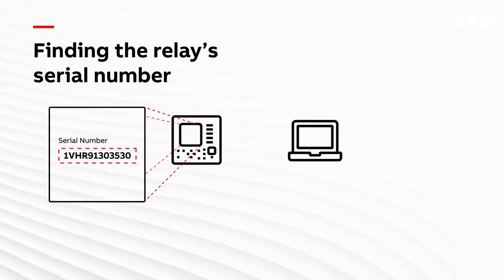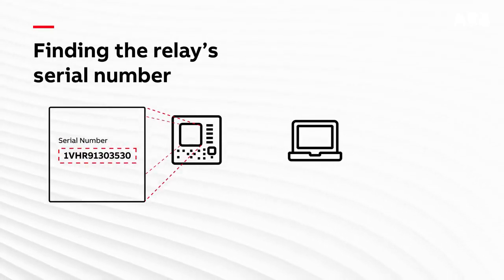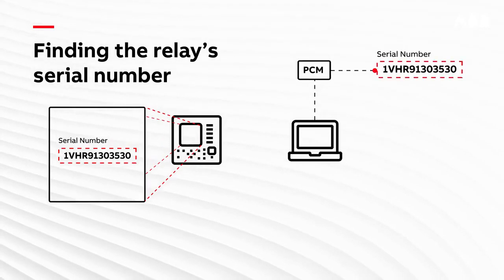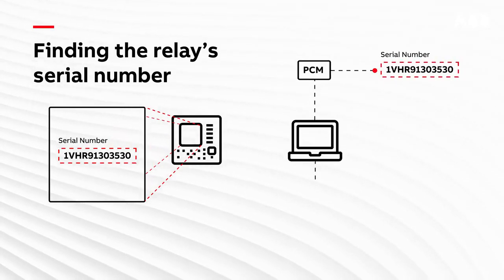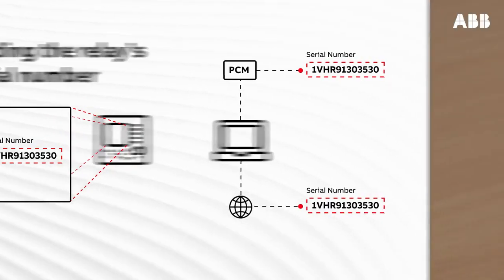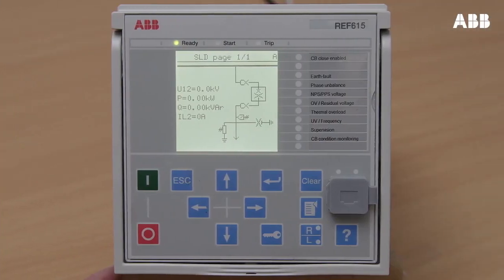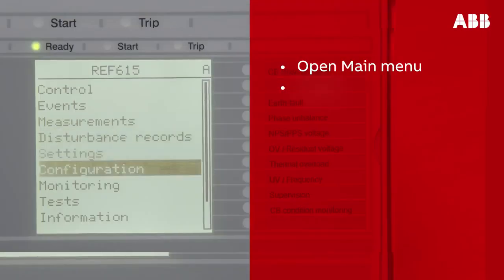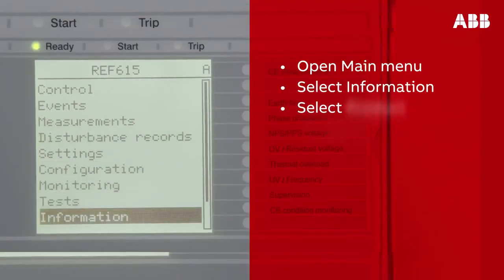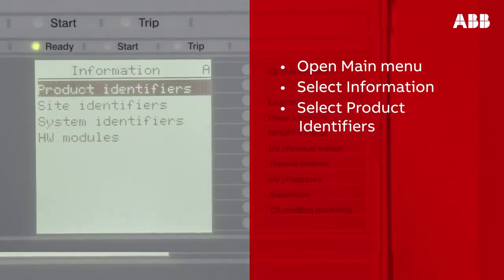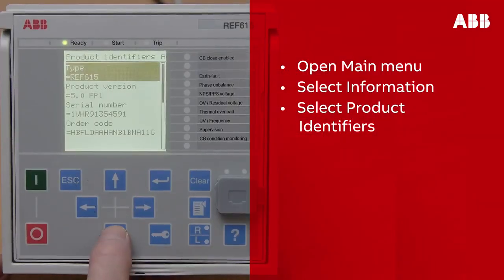There are three ways you can find the serial number: on the relay LHMI display, in PCM600, and on WebHMI. You can find the serial number by clicking the LHMI display on the relay. Open the menu and browse through to select Information, and then select Product Identifiers. Here you can see the serial number of the relay.